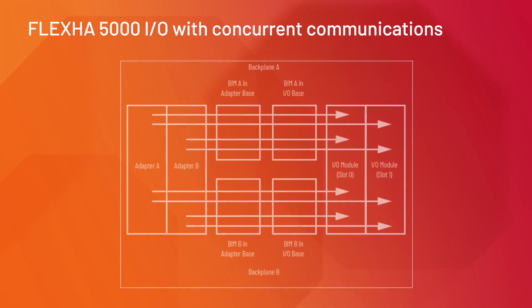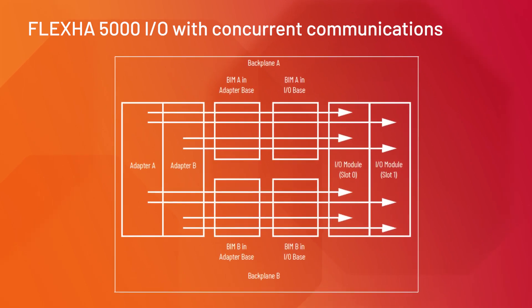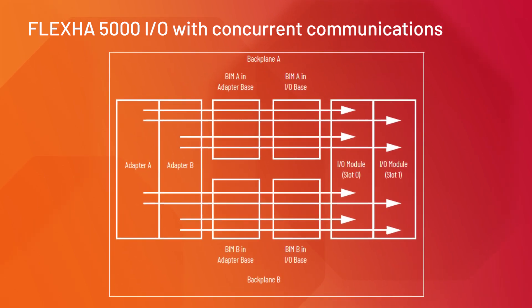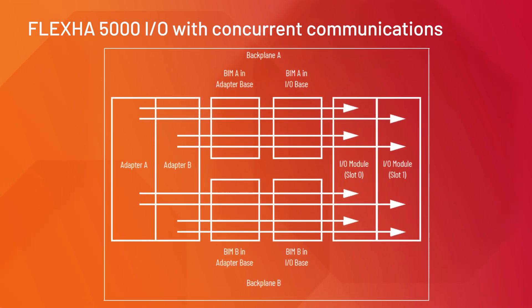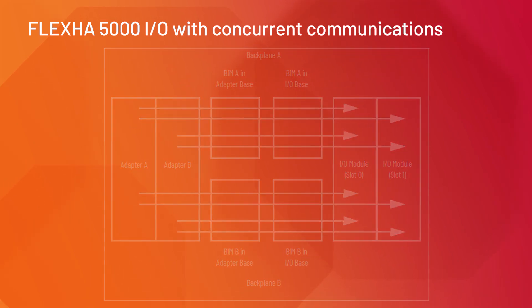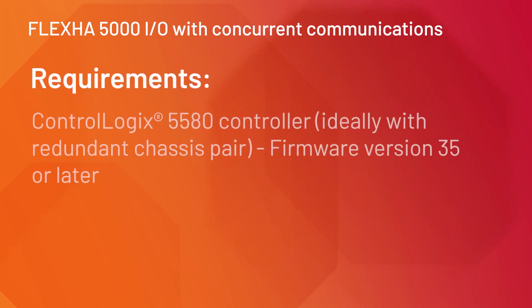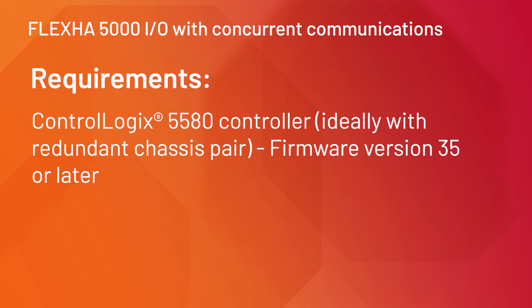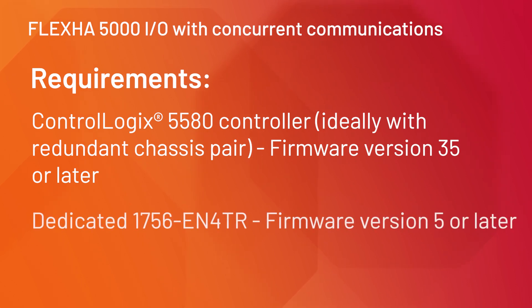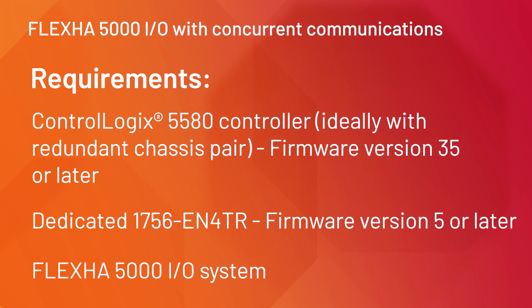The Concurrent Communications extend to the backplane and I/O modules. The requirements include a ControlLogix 5580 controller, ideally with a redundant chassis pair and firmware version 35 or later, a dedicated 1756-EN4TR with firmware version 5 or later, and a FlexHA 5000 I/O system.